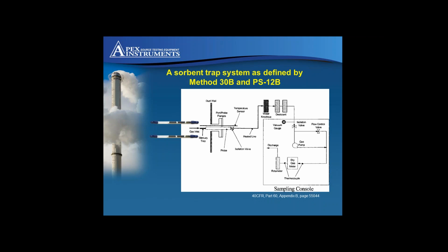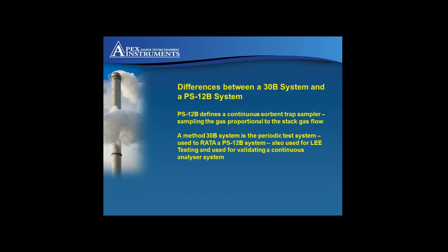PS12B also states that sampling must be performed proportionally to the stack flow. This is simply done by taking a flow signal from the source, sending this to the control console, allowing the system to then adjust the sample rate based on the flow rate. For both Method 30B and PS12B systems, they operate very similarly, and we try to keep both product lines as similar as possible, utilising the same component parts wherever we can. We are able to offer different packaging, different configurations, different materials of construction, and different probe lengths to meet site-specific requirements.